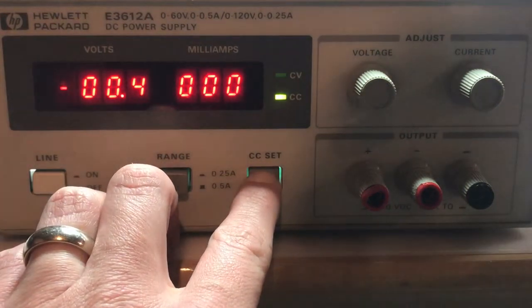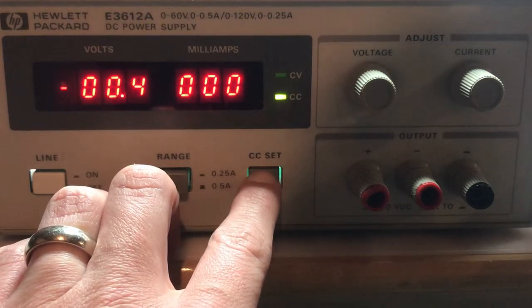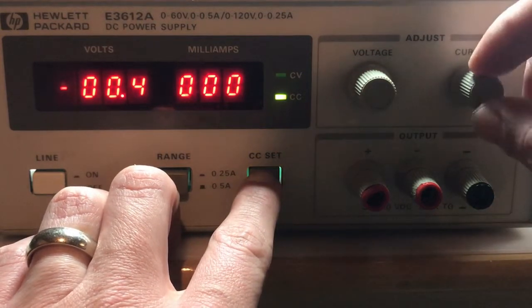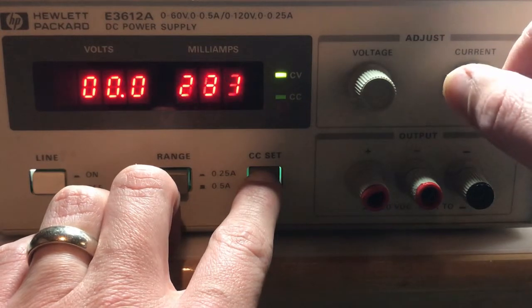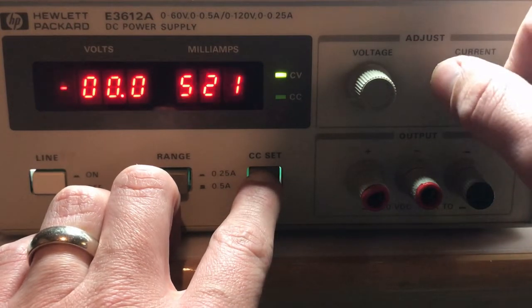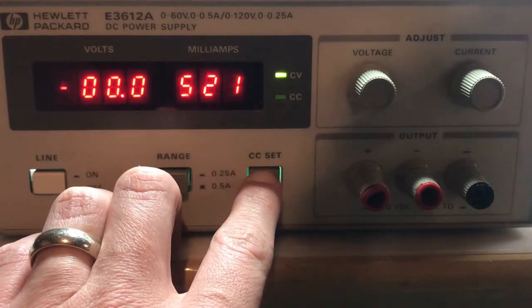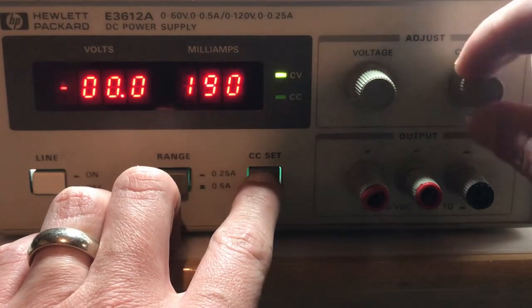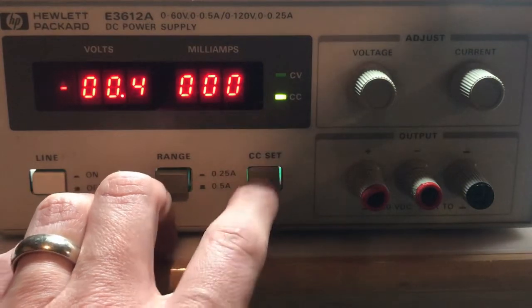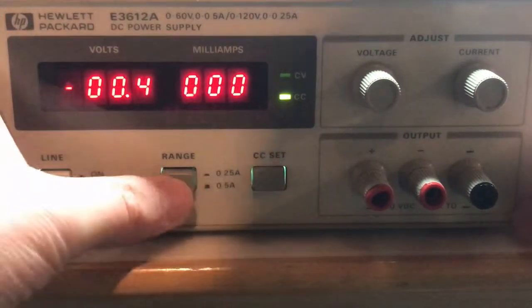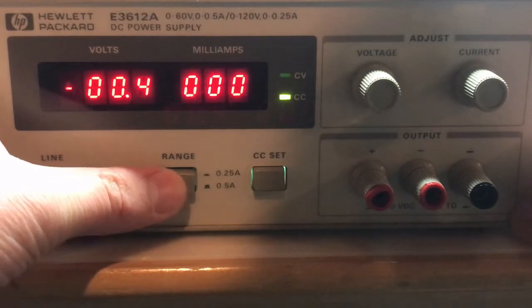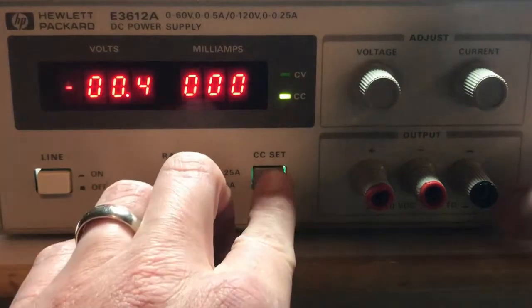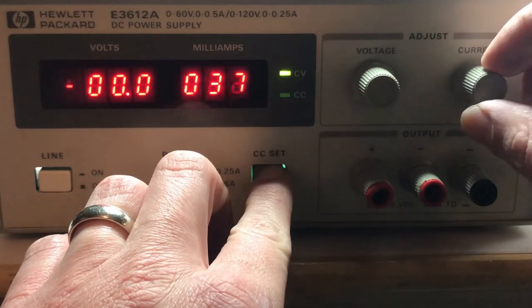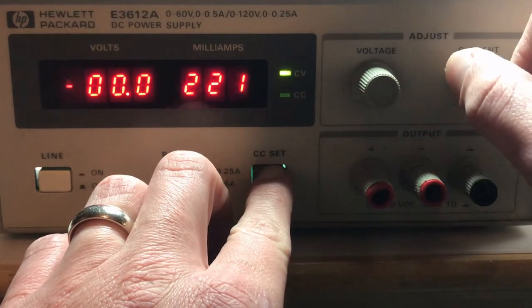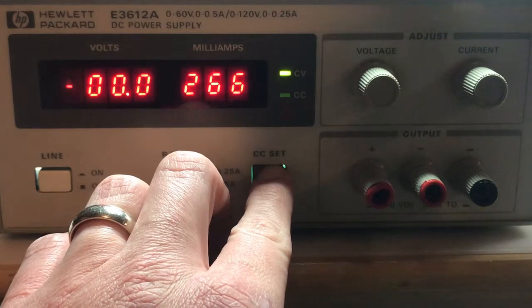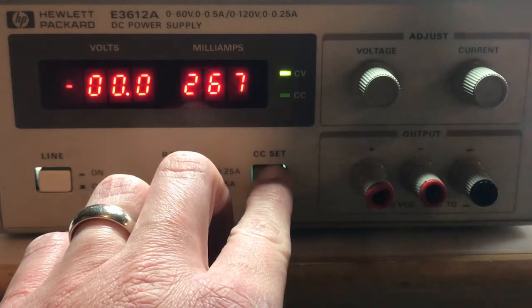Ooh, it's a good start. I'm holding in the CC set, and I have 0 displayed there. Let's see if I can get a current reading. I can. Great, it goes up to 520 and back down to 0. Let's go to the other range, the 0.25 amp range. Still reading 0. And 266, just above a quarter amp. Looks great.